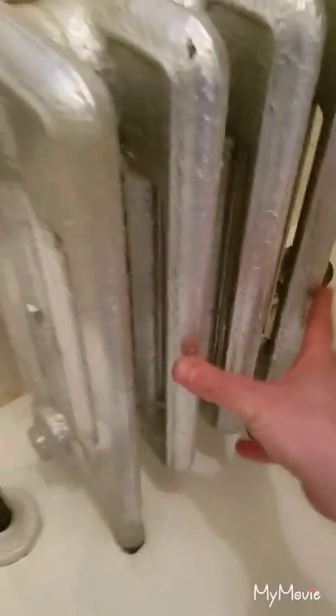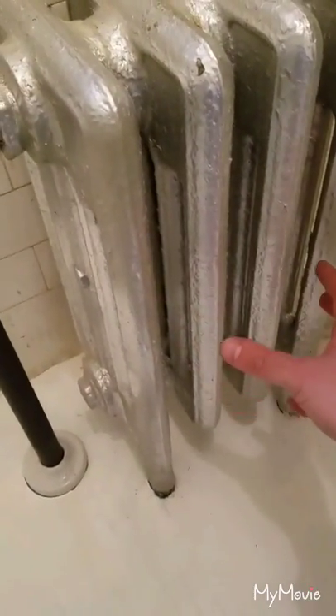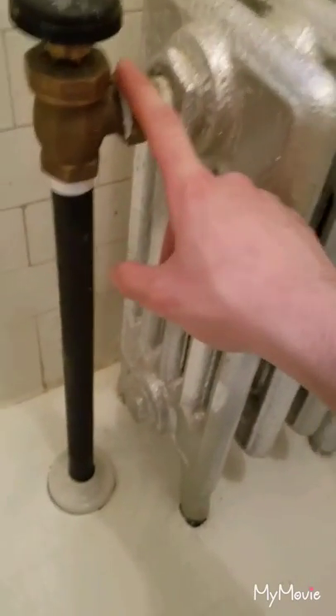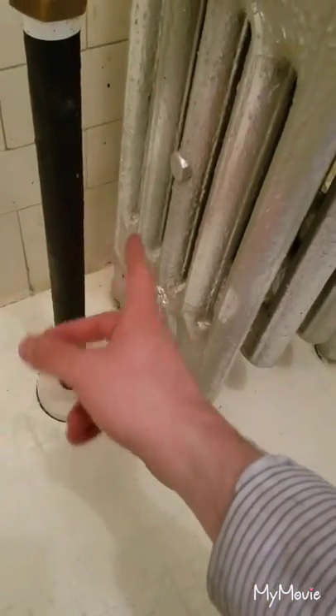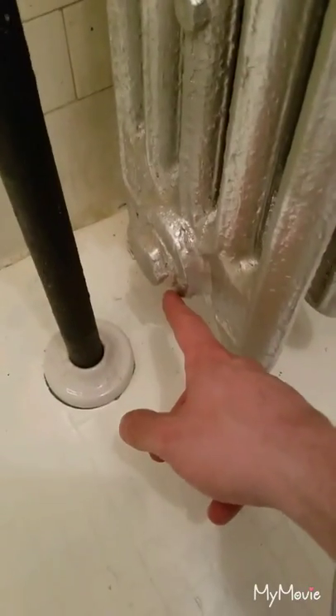So the steam would come in the radiator, the air would push out. The steam heats this up. And on the one-pipe steam system, this is going to be at the bottom because you're using the same pipe as the condensate return. So this wouldn't be at the top, it would be at the bottom. And the air vent would be up here.